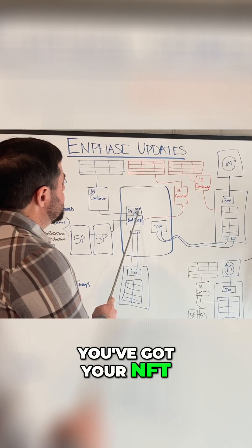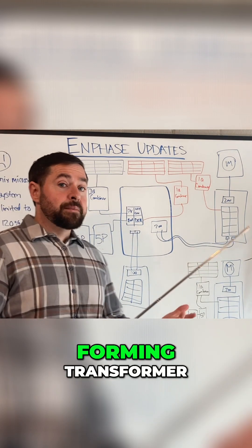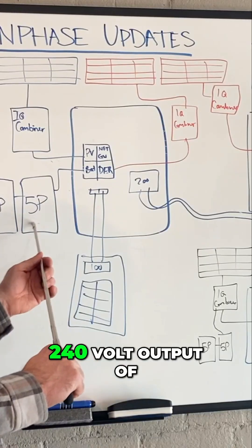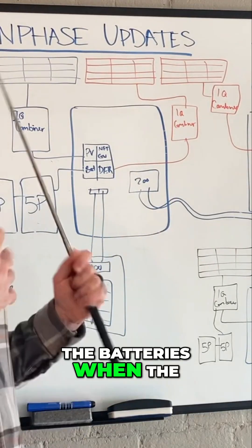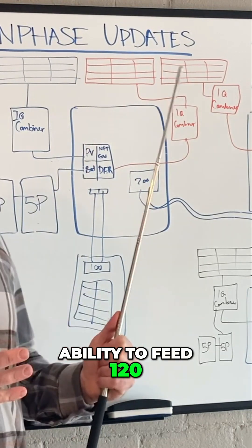Next, you've got your NFT breaker up here in the upper right. That is a neutral forming transformer. That's what takes the 240 volt output of the batteries when the system is off grid and gives it the ability to feed 120 volt loads.